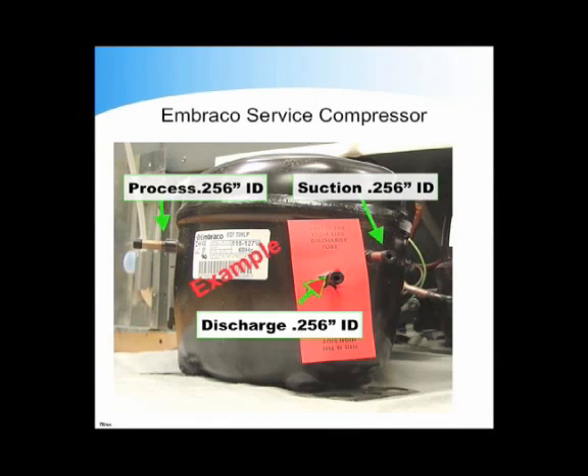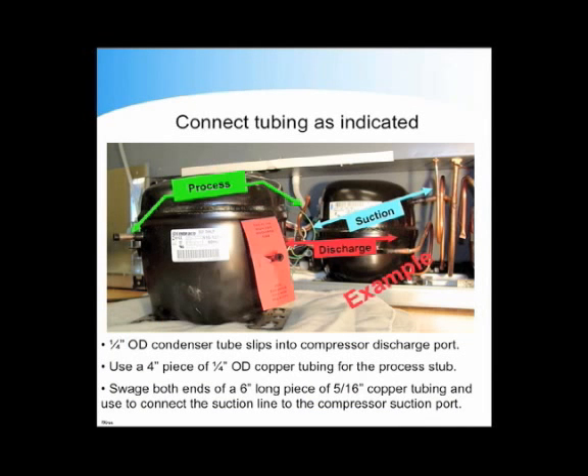Embraco service compressor. All compressor stubs are 5/16 of an inch OD. Connect tubing is indicated. The 1/4 inch OD condenser tube slips into the compressor discharge port. Use a 4-inch piece of 1/4 inch OD copper tubing for the process stub. Swage both ends of the 6-inch long piece of 5/16 inch copper tubing and use it to connect the suction line to the compressor suction port.